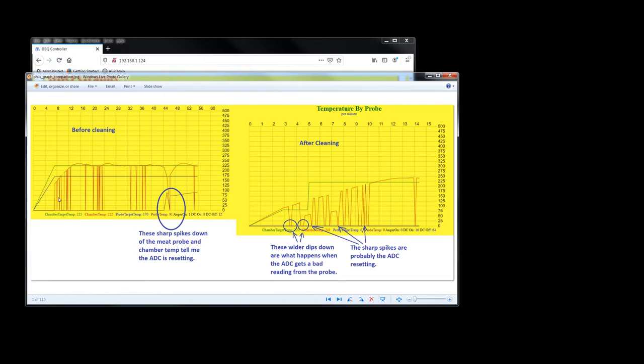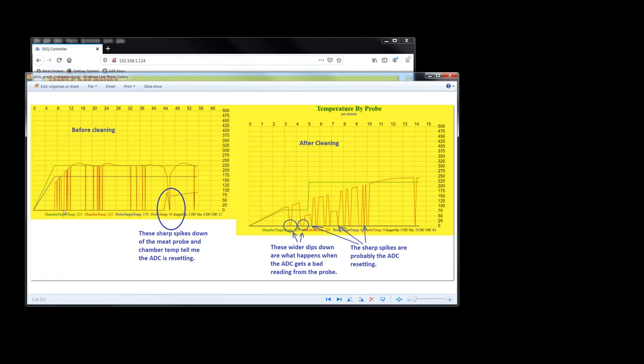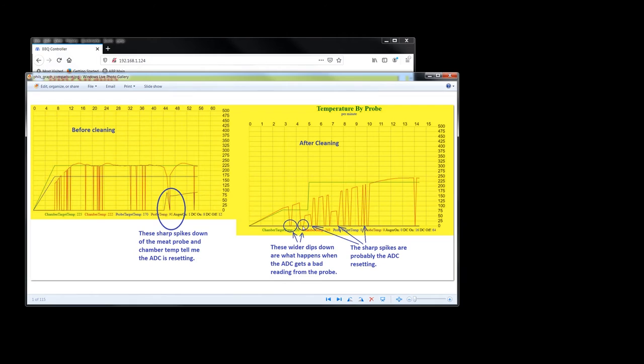And by the way, as you can see from the temp, the temperatures right here, when it's doing this doesn't really affect the operation. Well, these big ones will, but these little down spikes right here won't really affect the operation of it unless it dwells on zero. And that's, usually this dwelling on zero is a bad probe input.